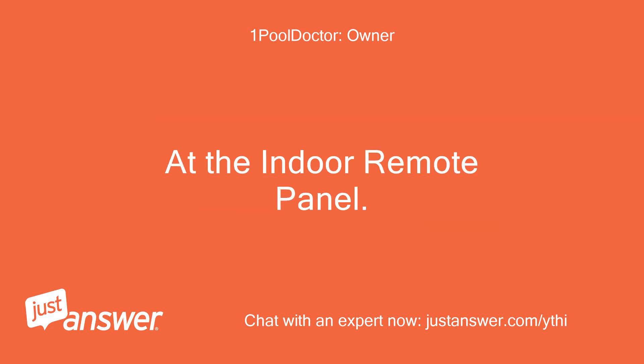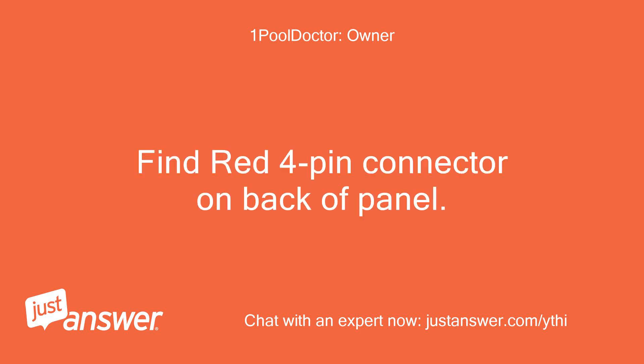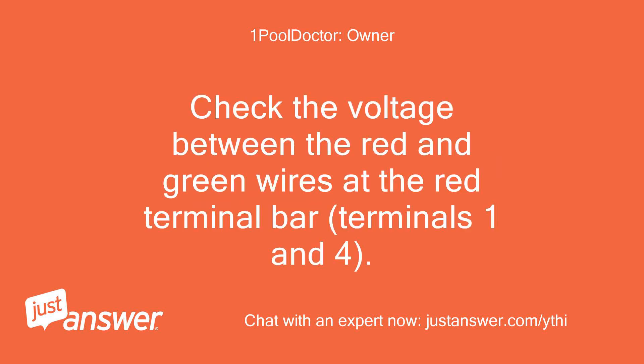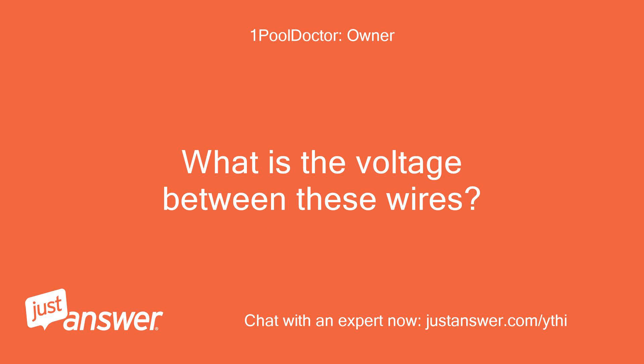At the indoor remote panel: Remove panel from wall holder. Find the red 4-pin connector on the back of panel. Check the voltage between the red and green wires at the red terminal bar, terminals 1 and 4. What is the voltage between these wires?